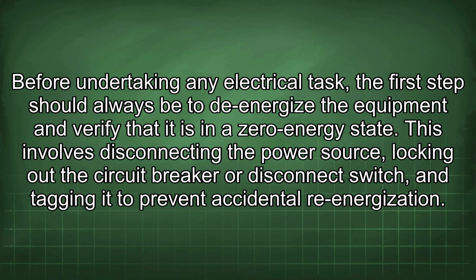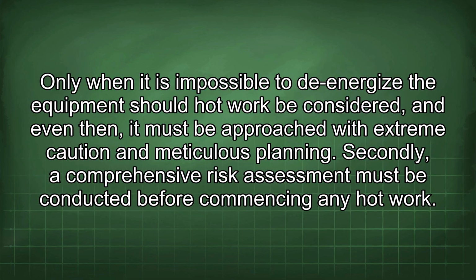Before undertaking any electrical task, the first step should always be to de-energize the equipment and verify that it is in a zero-energy state. This involves disconnecting the power source, locking out the circuit breaker or disconnect switch, and tagging it to prevent accidental re-energization. Only when it is impossible to de-energize the equipment should hot work be considered, and even then, it must be approached with extreme caution and meticulous planning.